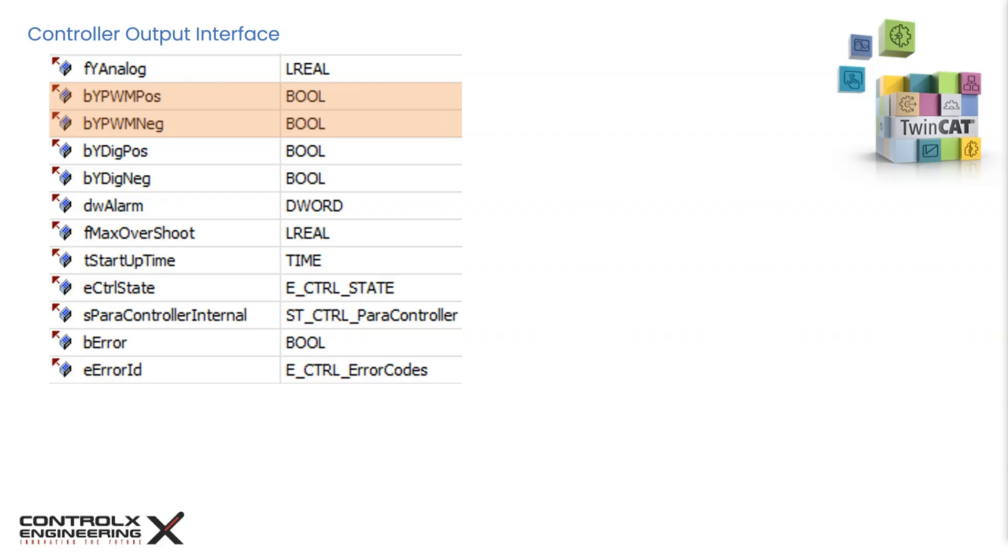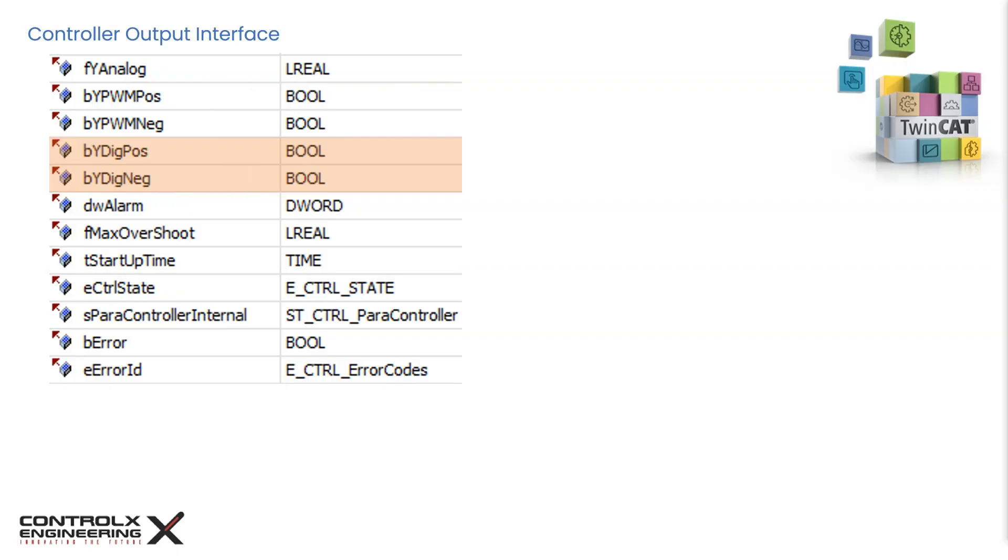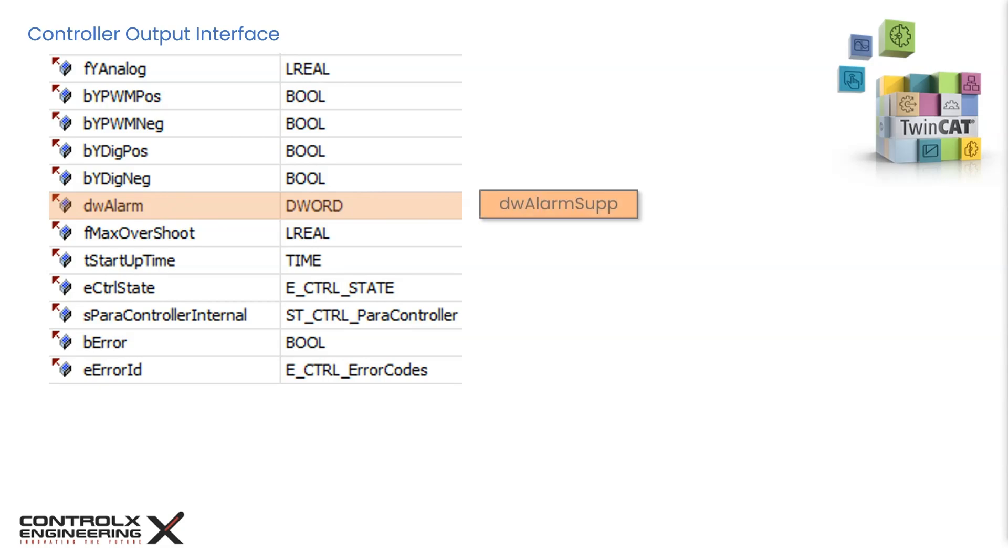These two digital outputs indicate if the controller is actively heating or cooling. The positive output stays true when controller is heating, otherwise it remains false. Similarly, the negative output stays true when the controller is cooling, otherwise it remains false. This is an alarm output of data type double word. Specific alarm types can be suppressed using the alarm suppression double word in the general parameters that we reviewed.